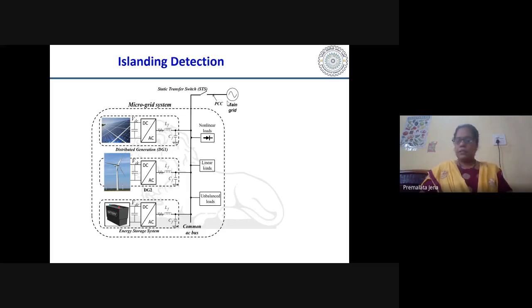Yes, it needs the grid frequency or voltage as a reference - the controller of the inverter needs this. But the point is, when the grid is off, the inverter will not stop its operation immediately, because it will take some different frequency as previously stored. So it will operate, but it will violate the voltage and frequency at the grid level. That is one point. Anybody wants to share any thought process?